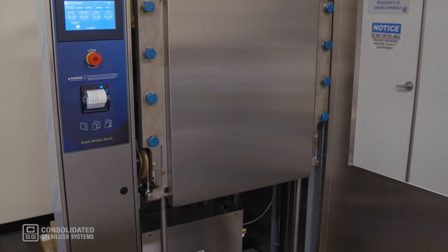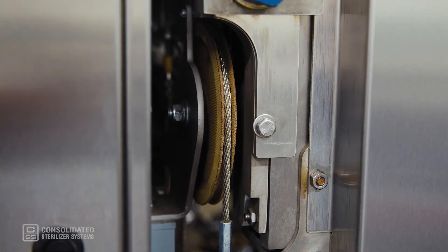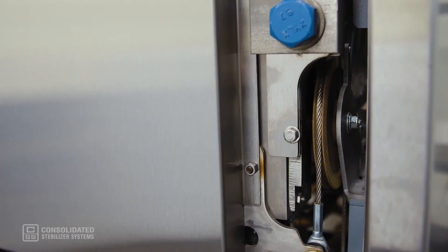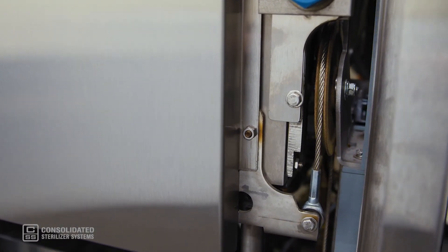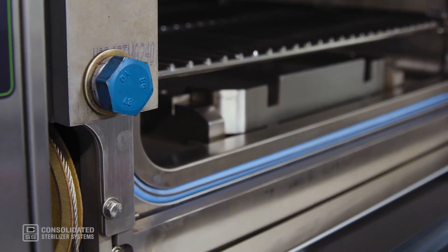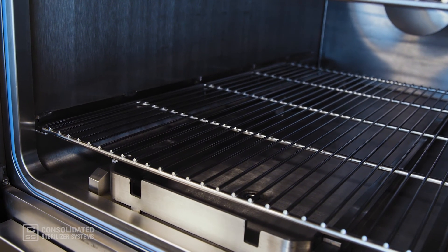Take a look inside and you'll see that this autoclave uses strategically positioned wall-mounted pulleys to reduce the wear and tear of steam corrosion. In addition, the easy glide door mechanism uses counterweights and pneumatic actuators, eliminating maintenance issues associated with motors, hydraulics, or water pistons.